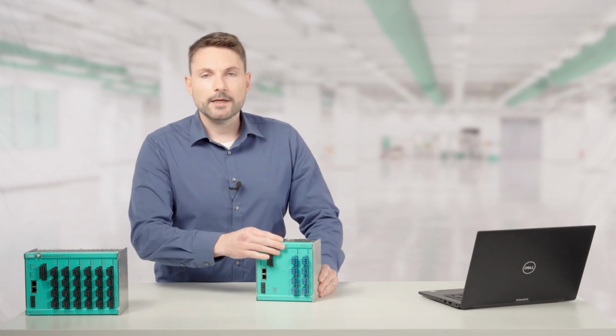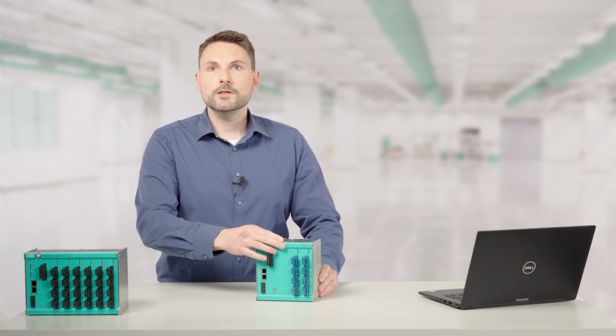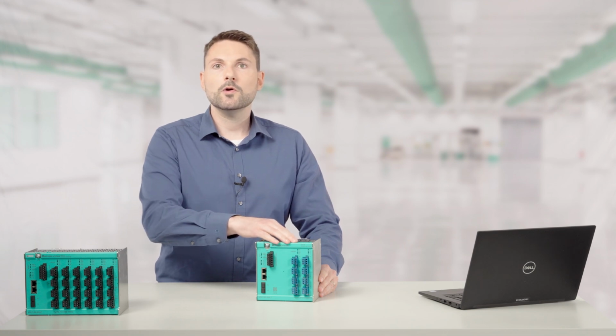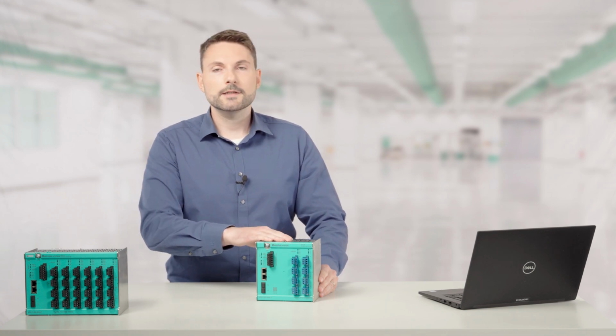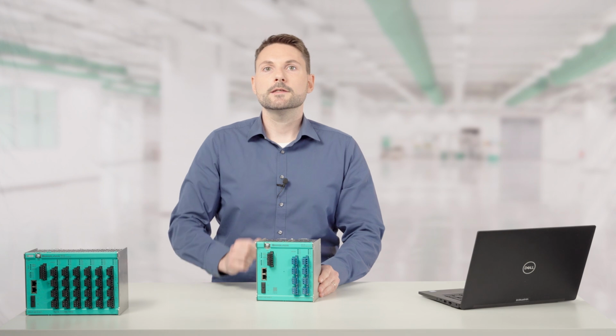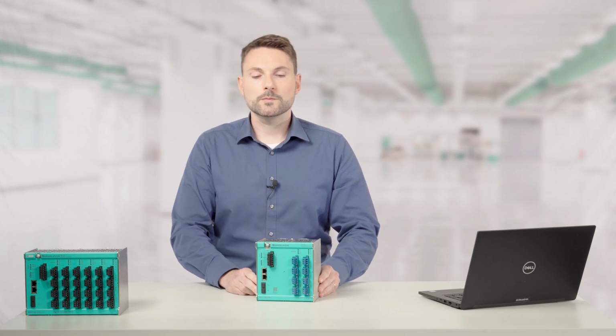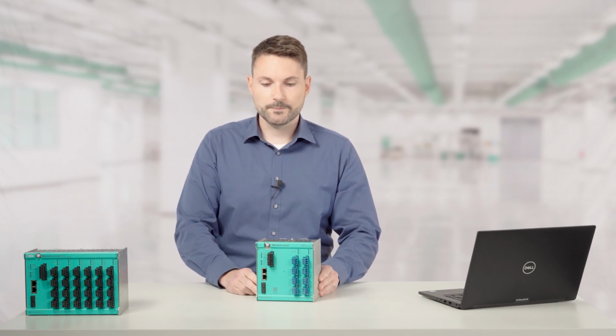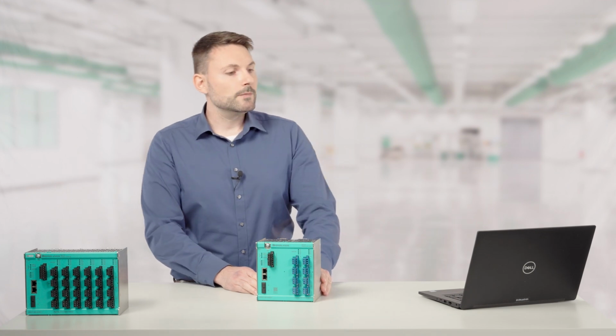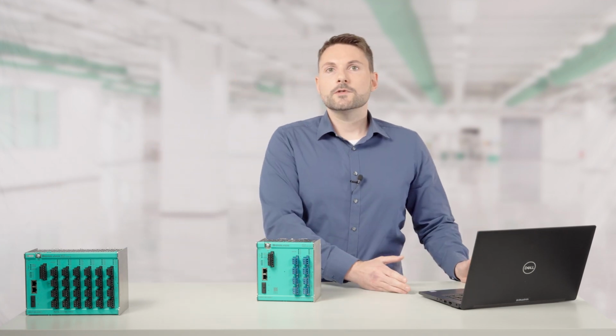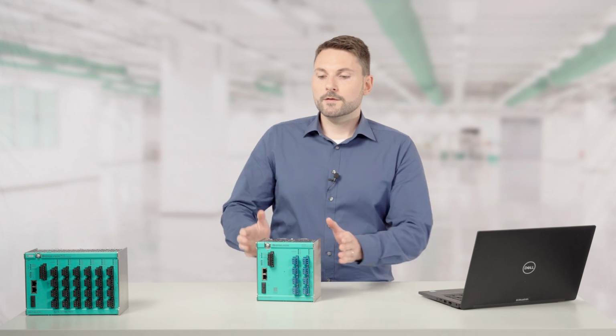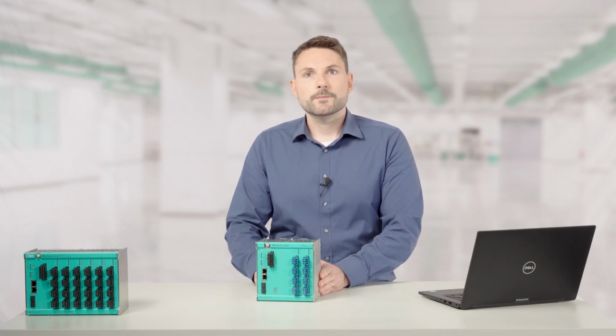Depending on the variant, we have 8, 16, or 24 Ethernet-APL spur ports and, in the variants with integrated Profibus PA proxy, the Profibus PA field devices can also be connected in addition to the Ethernet-APL field devices. For commissioning, we need a computer from which we want to start commissioning, the switch, and a network.